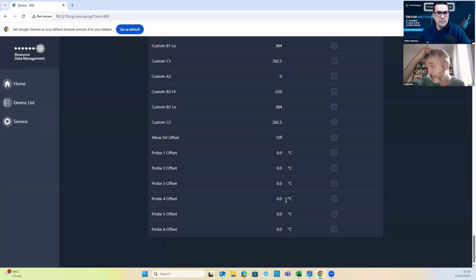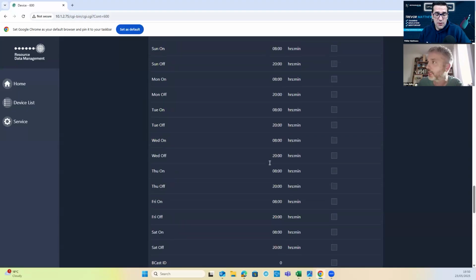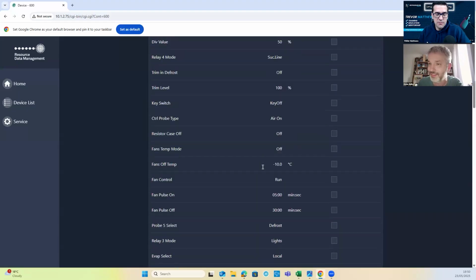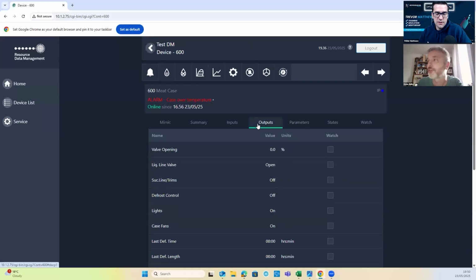If you've got really long cables, again, we've talked about before, if you've got really skinny cable and really long runs, that cable is going to carry a resistance. And on PT1000 probes, 4 ohms per degree, that's going to affect your reading. And so you're going to measure the resistance of that cable and offset your probes in here so that you don't get crazy readings. Okay. So more than big, I see it more in industrial stuff now too. Yeah, 100%.